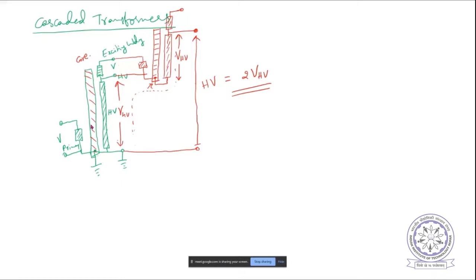So even with two transformers or a single transformer, the problem is you have to make a single unit of so much height, and so much engineering is required inside. Transporting that single unit itself is a big challenge, because the roads in a developing country may not be fit for transporting such a large transformer. So that is also an issue. Therefore, we have to go for the cascading transformer. Throughout the world, beyond 500 kilovolts, we will not use a single unit.